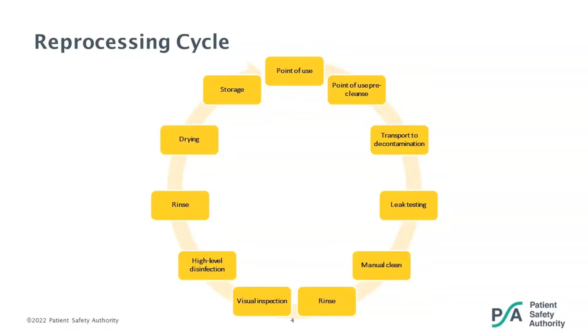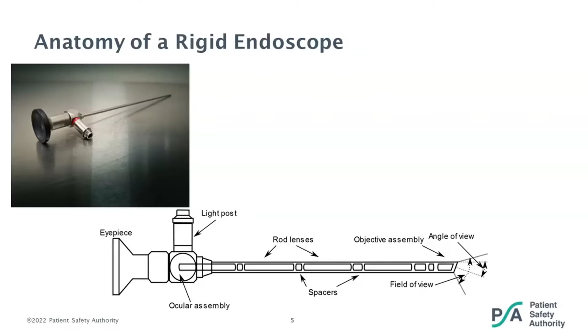So just a little bit about the anatomy of rigid endoscopes. This is a device that has minimal flexing of the shaft that can be damaged if the scope is flexed beyond its limits. It can be video or non-video. It could have a video chip mounted at the distal end of the scope, and sizes range from 1.9 millimeters to 15 millimeters. Fiber optics are housed between the inner and outer tubes and transmit light from the light post to the distal end of the endoscope. And these endoscopes are used to perform surgery and can have a working channel that allows the surgeon to pass instruments.